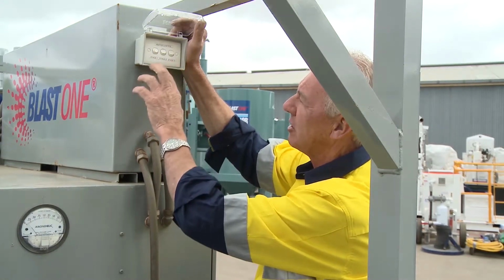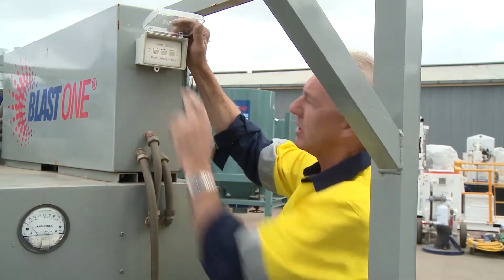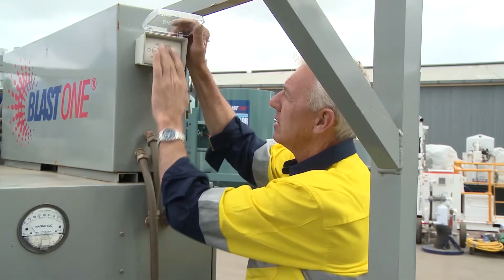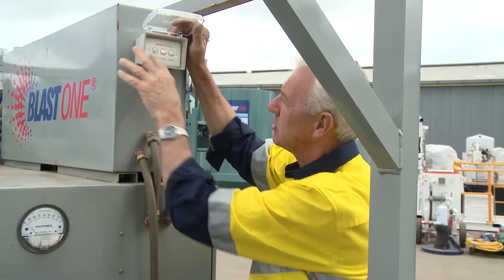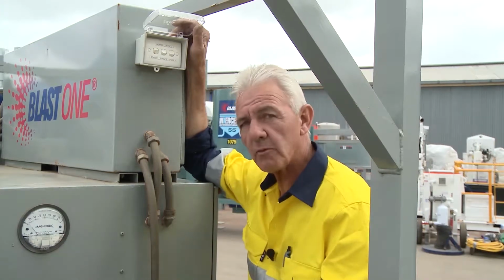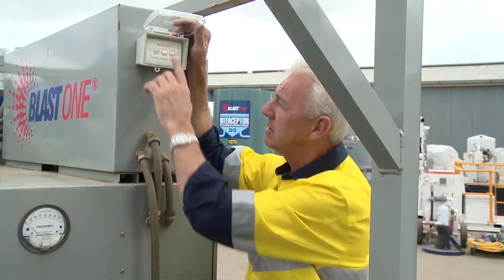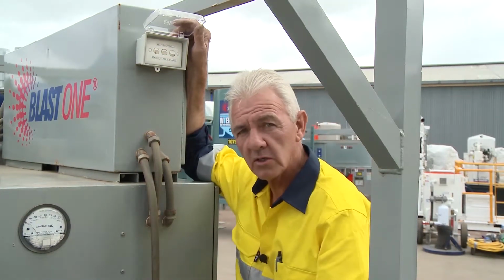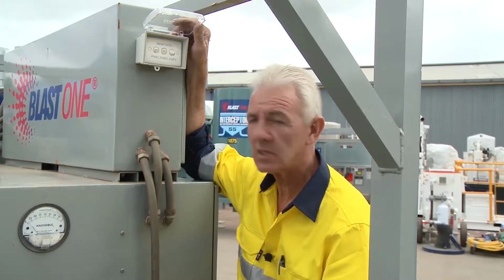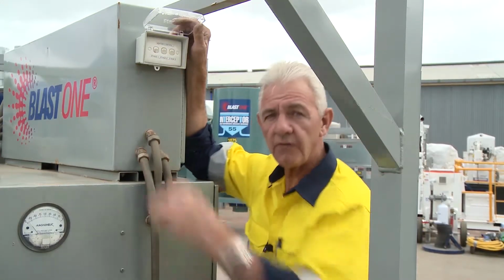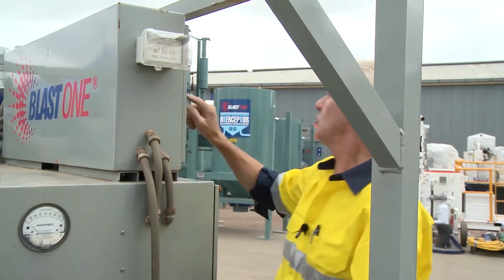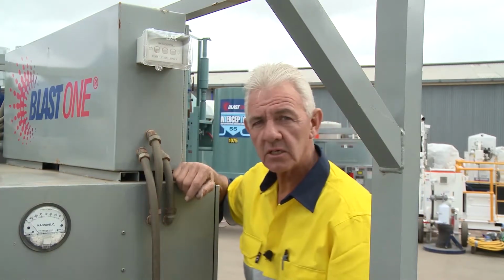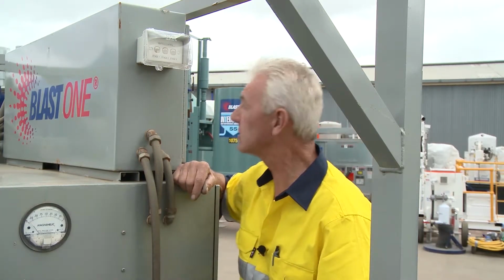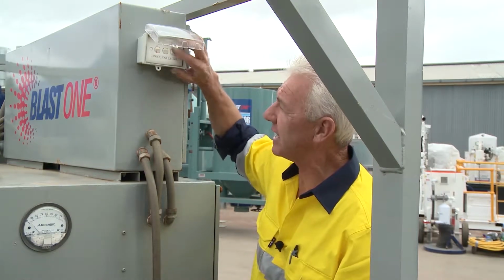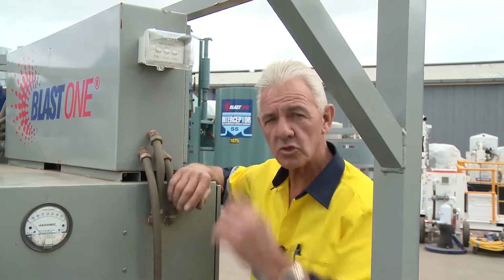So the whole idea is you don't go 1, 2, 3 straight up - it's a periodic process. You'll turn stage 1 on, wait a few moments, that'll click in, turn stage 2 on, wait a few moments, then turn stage 3 on. If you load them up too quickly, you'll get a shutdown light illumination, so you know you have to take your time turning them on.